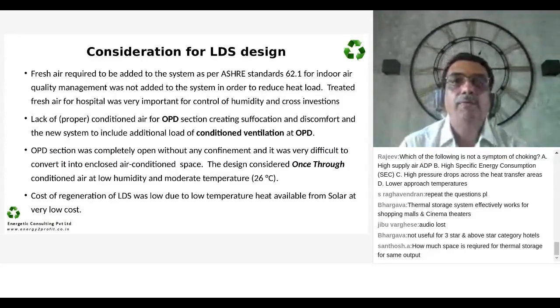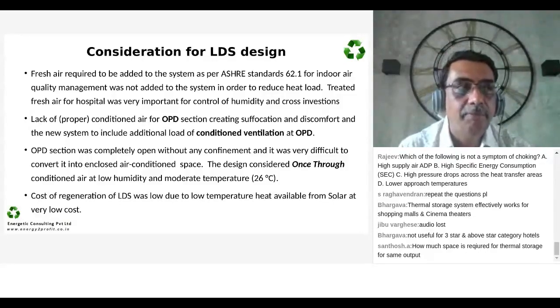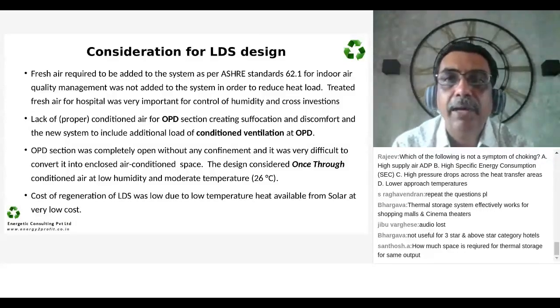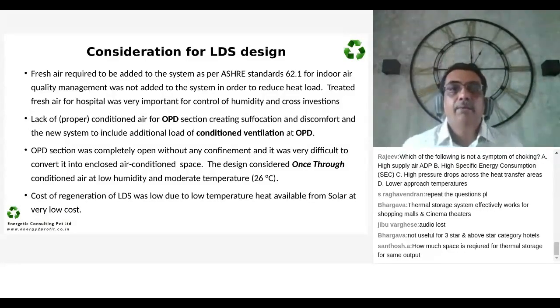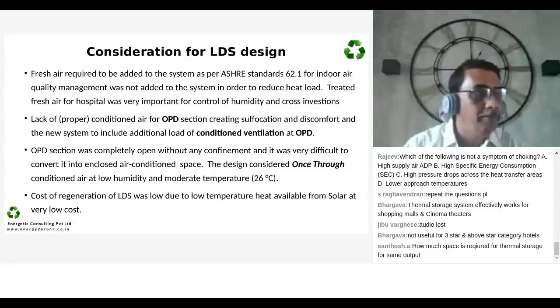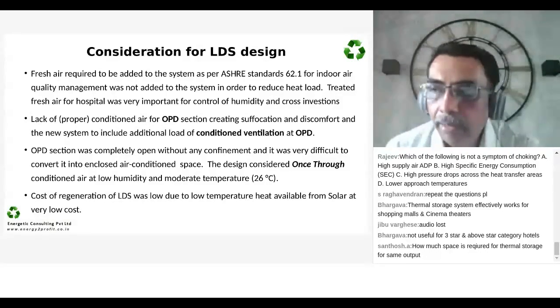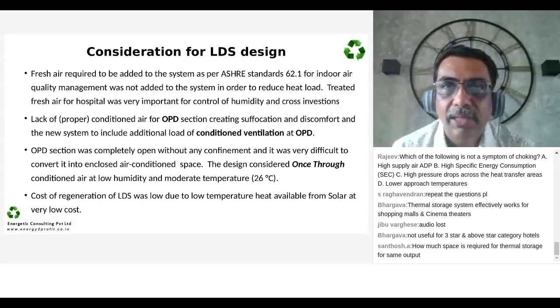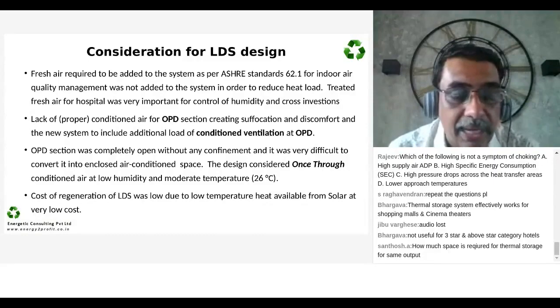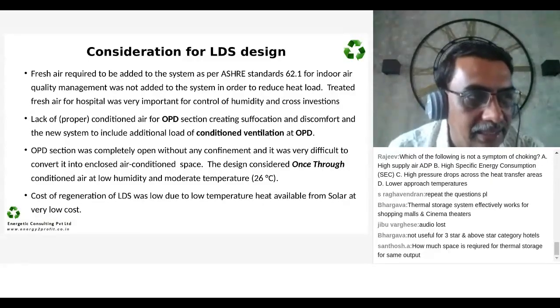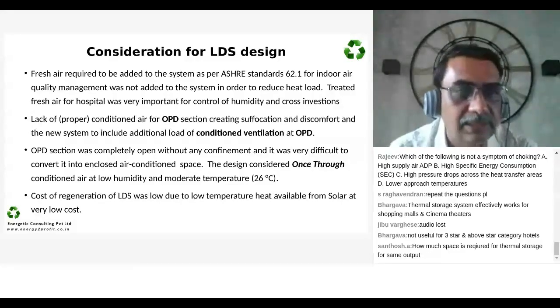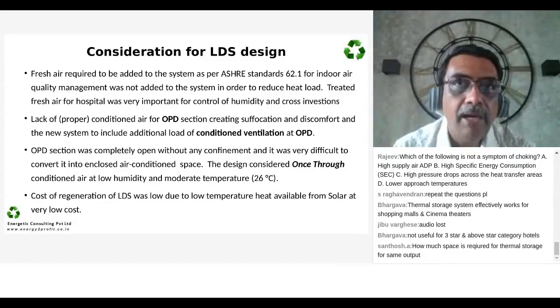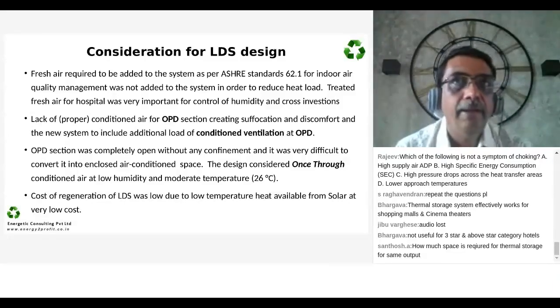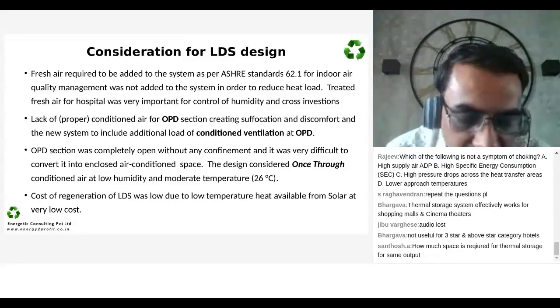Thank you, sir. Now, we have a consideration of a liquid desiccant system, where I told you some time back that the fresh air required as per ASHRAE standard 62.1 for indoor air quality was not maintained. So we added a liquid desiccant system for that. And second, very interesting, there was a large OPD, and post-COVID, if there are any people from the healthcare industry, there is a mandatory requirement for certain areas, and most facilities are missing this point, that the outdoor patient sections, OPD sections, should have 100% fresh air, no recirculation of air. The cost of that is very high if you go with the conventional air conditioning system.